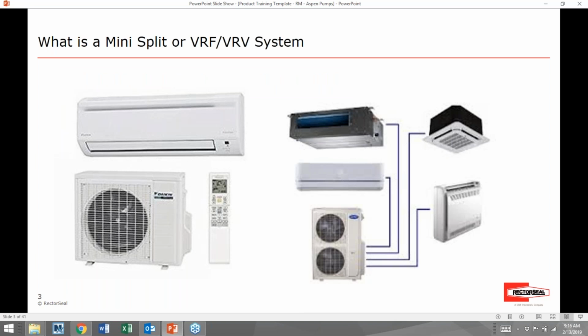So first, what exactly is a mini split or a VRF or VRV unit? On the left-hand side of the screen, you see a traditional mini split, one indoor unit to one outdoor unit. And what you see there is what we call a traditional high wall unit. This is the majority of what we're going to be talking about today with the use of Aspen pumps. On the right-hand side, you'll see our VRF or VRV equipment. Just a quick note on the differentiation between VRV and VRF: VRF is variable refrigerant flow and VRV is variable refrigerant volume. There's no real difference between the two, except that Daikin uses VRV and everyone else uses VRF. So for today's discussion, if you hear me use one or the other, I'm using them interchangeably.